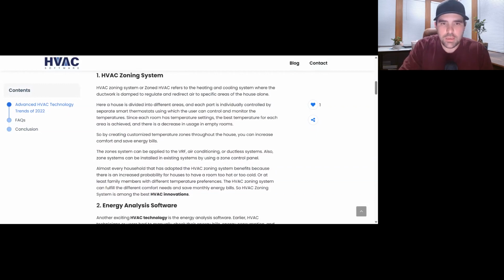So basically it refers to heating and cooling systems where the ductwork is dampered and regulated, redirecting air to specific areas in the house. What they mean by that is, just for a good example, the house that I'm in is a 1926 home, a really old house. The downstairs is nice and cold, the upstairs is always really hot. So the thermostat shuts off when the downstairs hits a certain temperature. Well, how can we combat that? We could zone it. We could put a sensor upstairs and a sensor downstairs, and put a couple zone dampers in there. So when the sensor downstairs is satisfied, the thermostat says, hey it's 70 degrees in here, let's close this zone damper, but we're still going to allow air to be pumped upstairs until that sensor or thermostat is also satisfied. And then that zone damper will close too. Ideally, your HVAC system is backing down based on how much need or load it has.